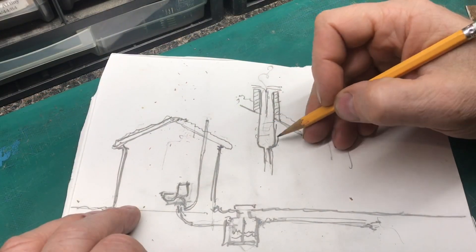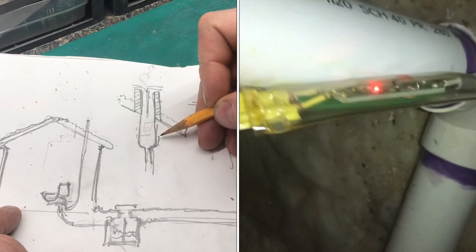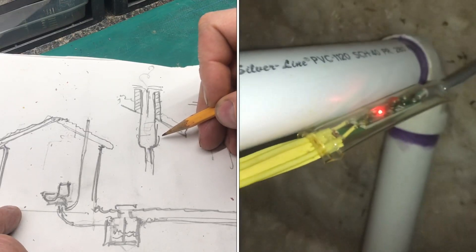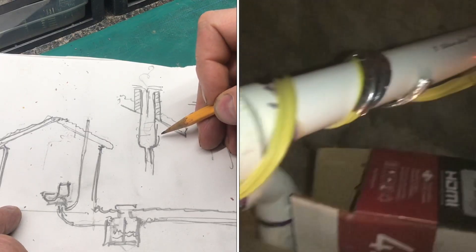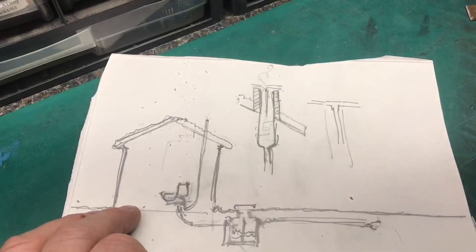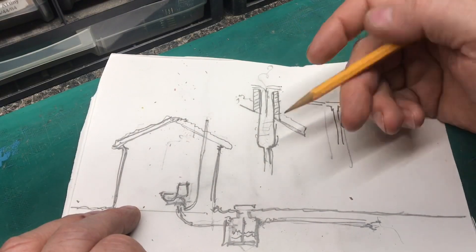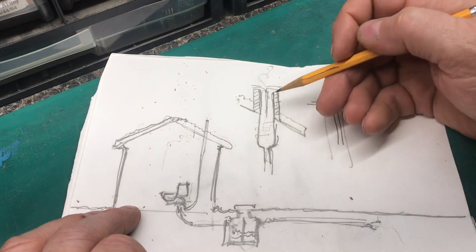Now the heat tape that we used has a thermostat so it only comes on when it's about 32 degrees and we only turn it on when it is blocked.